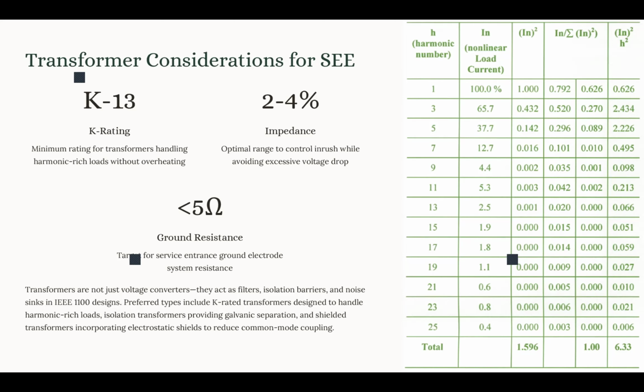And if we go higher than 4%, it would cause excessive voltage drop when we have dynamic load changes. So we balance those problems by setting the impedance between 2 and 4%. This way we make sure we control inrush current and we have minimal voltage sag propagation.